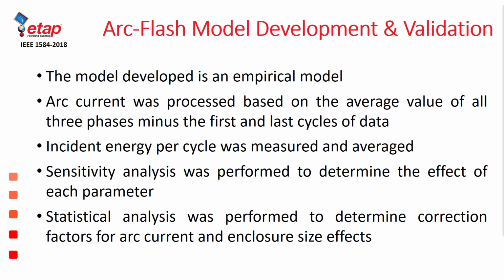However, expected arc flash physical behavior was also factored into the model development to prevent it from having abnormal behavior, like its predecessor did in some cases. Examples of previous abnormal behavior of the 2002 model include conditions under which the model could even predict the arc current being higher than the corresponding bolted short circuit current. This was definitely eliminated and corrected as part of the 2018 model.